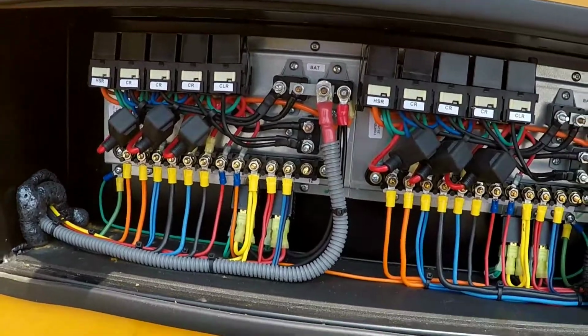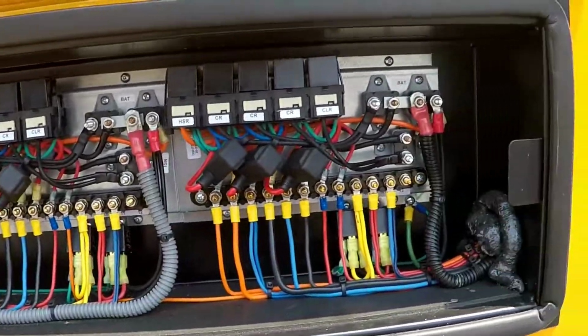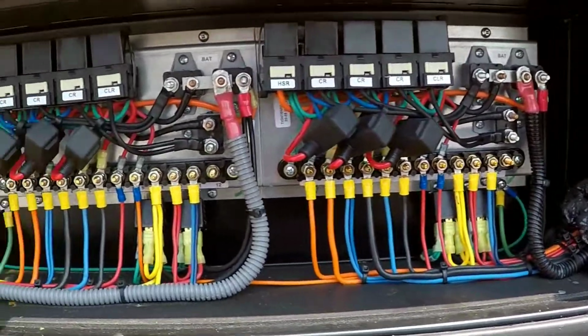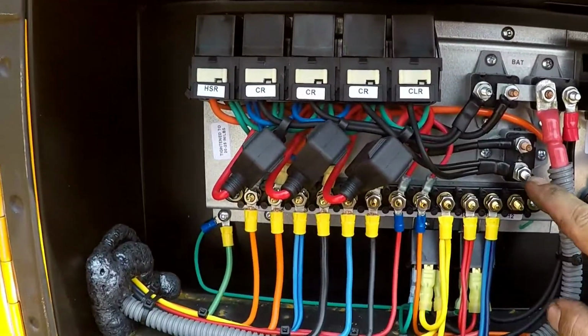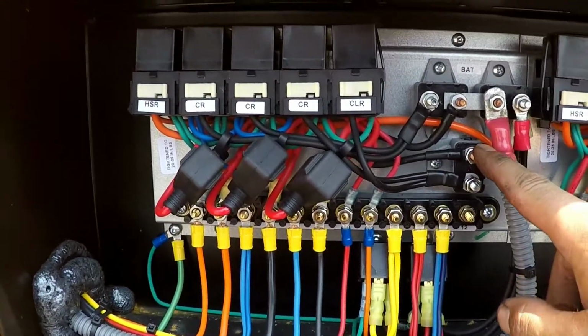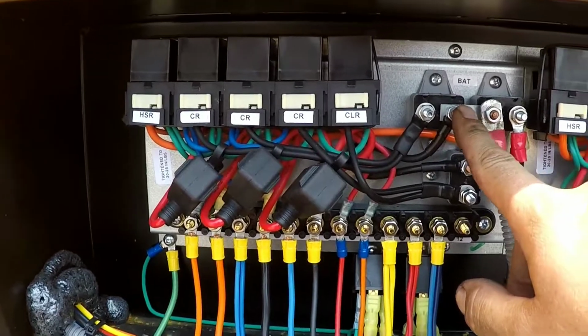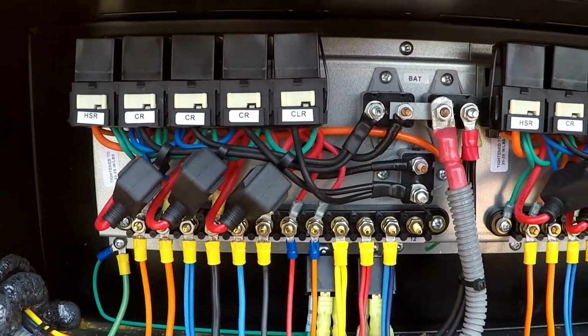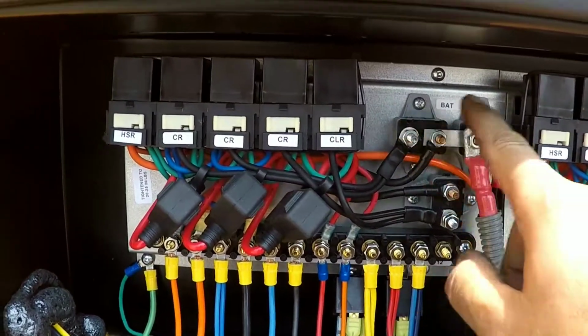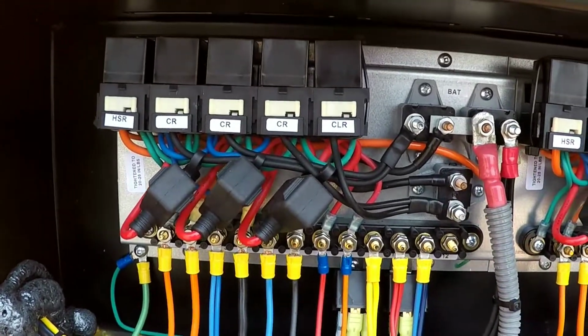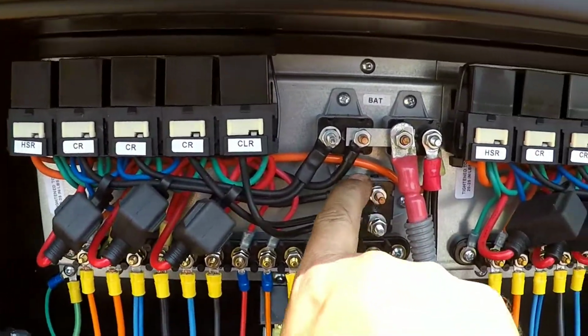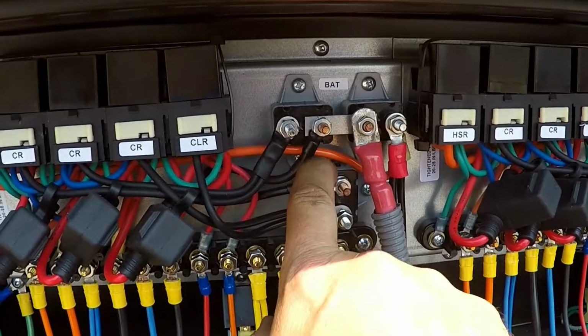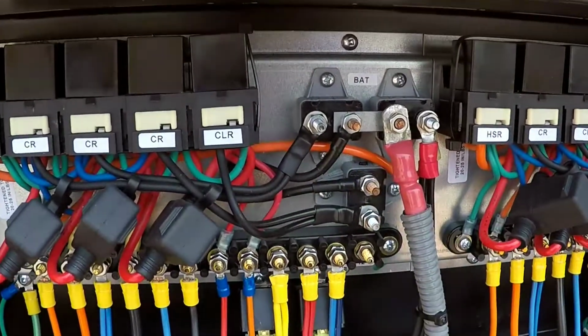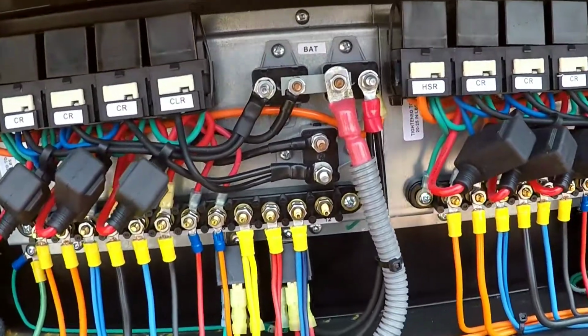This is where all your relays and circuit breakers are, and all your wiring for your rack air conditioning system. You want to make sure that none of these breakers here are tripped. You want to test these with either a regular test light or some type of power probe. See if you have power coming on both ends of the breaker. If you don't, you can try and reset the breaker with this little black button right here with a small screwdriver. See if the breaker resets. If it does not, perhaps you need to replace it.